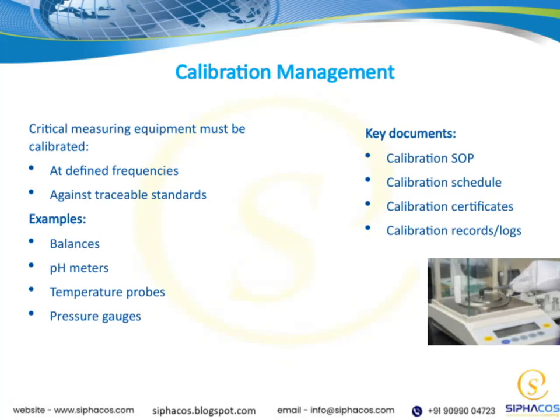Let's talk about calibration management, which is a crucial part of maintaining quality and accuracy in our processes. First, we need to ensure we have the key documents in place, such as the calibration SOP, which outlines the procedures we follow. We also need a calibration schedule to keep track of when each piece of equipment requires calibration, along with calibration certificates that serve as proof of compliance. Additionally, maintaining detailed calibration records, or logs, helps us keep an ongoing history of each instrument's performance.